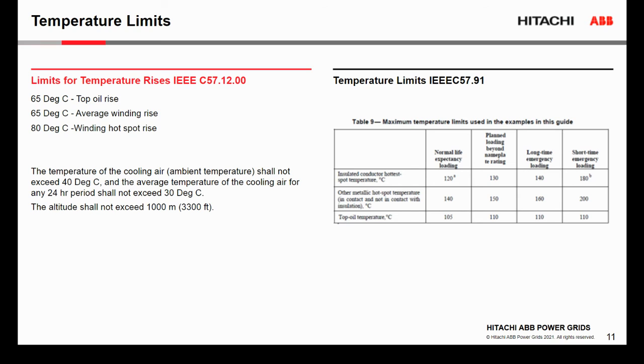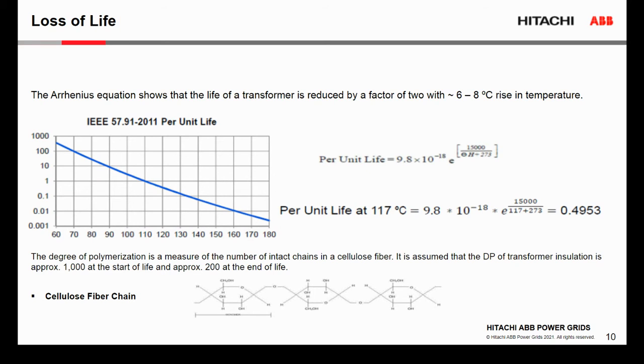So, loss of life. By increasing the temperature of the hotspot, we change the loss of life. We reduce the life of the transformer. So, if we increase the hotspot by 6 to 8 degrees C, we may reduce the life of the transformer by a factor of 2.